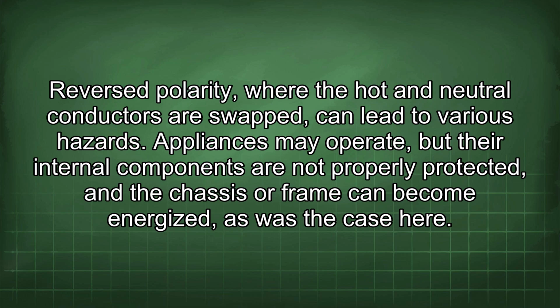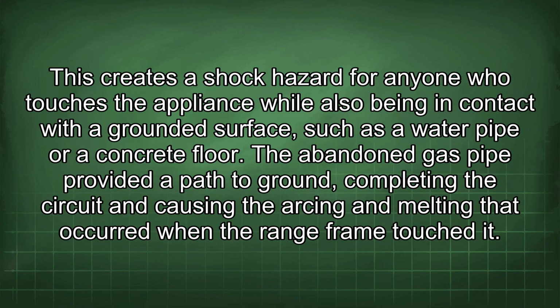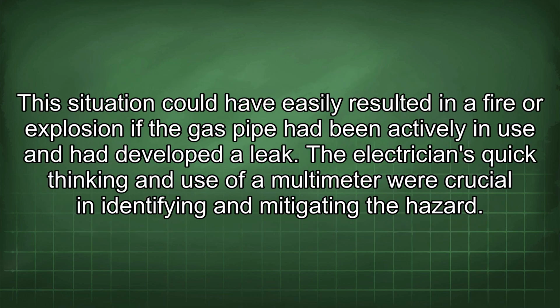Reversed polarity, where the hot and neutral conductors are swapped, can lead to various hazards. Appliances may operate, but their internal components are not properly protected, and the chassis or frame can become energized, as was the case here. This creates a shock hazard for anyone who touches the appliance while also being in contact with a grounded surface such as a water pipe or a concrete floor. The abandoned gas pipe provided a path to ground, completing the circuit and causing the arcing and melting that occurred when the range frame touched it. This situation could have easily resulted in a fire or explosion if the gas pipe had been actively in use and had developed a leak.